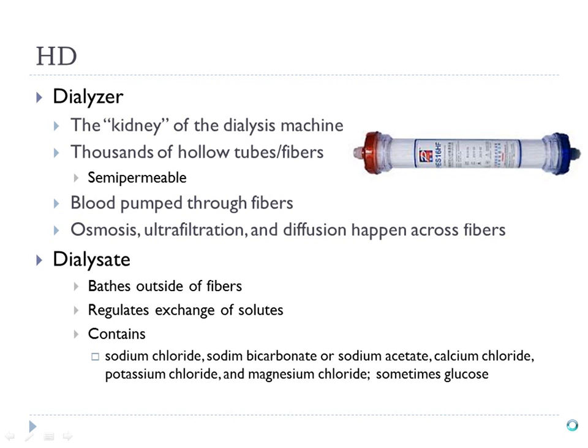On the outside of the fibers, they are bathed with a dialysate. With hemodialysis, the dialysate is non-sterile. This solution contains potassium, calcium, and all types of things in a normal range level. The purpose is to create a concentration gradient for diffusion.